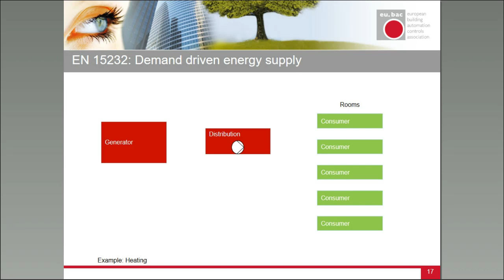The way described in this standard is that you have to see the demand for heating or hot water in the rooms. That means the consumers in the rooms have to tell you how much energy they really need to maintain a certain level of comfort. Just imagine a room that's not occupied does not necessarily need to be heated. So if we install a building automation control system in our rooms, we can easily detect whether people are present or not, even how many people are present. Based on that information, we can demand the necessary energy to maintain the level of comfort.